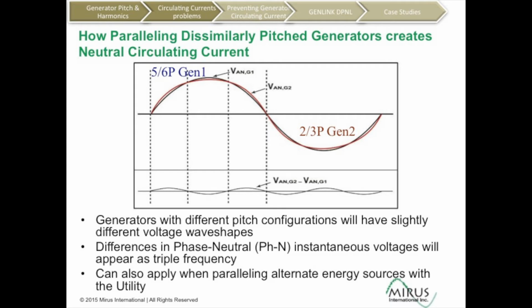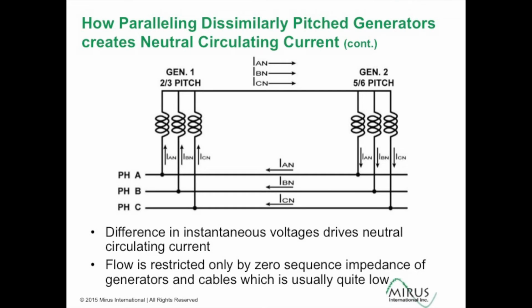Well, when we're paralleling, it doesn't matter where the voltage is being generated. It's the impedance of the system that's going to either block the flow or allow the flow. And 2/3 pitch generators have less zero sequence impedance to the flow of third harmonic. So when we're paralleling, if we have these instantaneous voltages, they're going to drive current in each phase through the phase conductors on the parallel bus back into the other generator, and then combine in the connected neutral, and circulate this way. So every phase has circulating currents that are the result of the dissimilar wave shapes. And the total of these currents is what shows up in the neutral. Or if the neutrals weren't connected but they were grounded, then the current would flow through the ground and then back into the other generator and back.